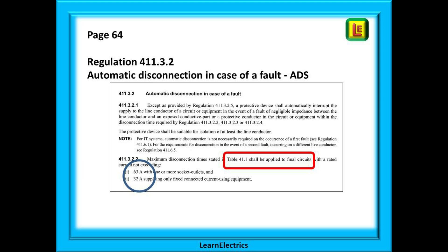The red box here tells us that table 41.1 on the next page only applies to final circuits. It also tells us that it only applies to circuits up to a certain size of amps as shown in the blue circle, 63 amps for circuits with sockets or 32 amps for fixed equipment.